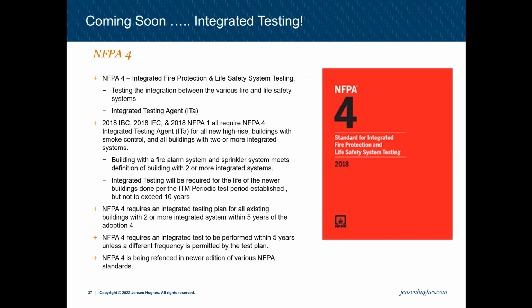Ensuring that systems do get tested is beneficial, not only because it's required by code. If a building owner or developer is making a building, designing these systems, and we all spend a lot of time designing and building them, if they don't work, it's like all that work has been done in vain. A building owner or manager would be stuck trying to fix these systems, whether it's smoke control, special inspections not done right, or integrated testing. They'll be forced to deal with these systems for the life of the building. Having to fix them is much, much more difficult than getting them installed correctly the first time.